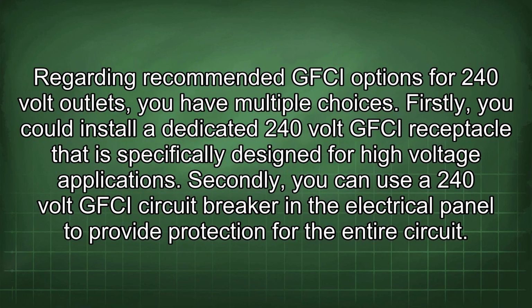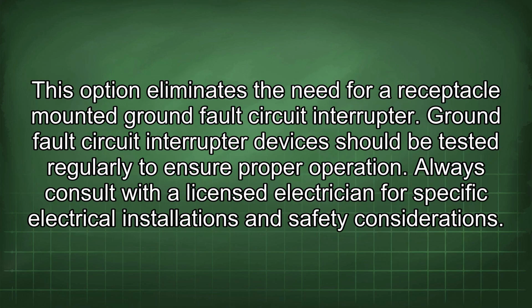Regarding recommended GFCI options for 240-volt outlets, you have multiple choices. Firstly, you could install a dedicated 240-volt GFCI receptacle that is specifically designed for high-voltage applications. Secondly, you can use a 240-volt GFCI circuit breaker in the electrical panel to provide protection for the entire circuit. This option eliminates the need for a receptacle-mounted ground fault circuit interrupter.